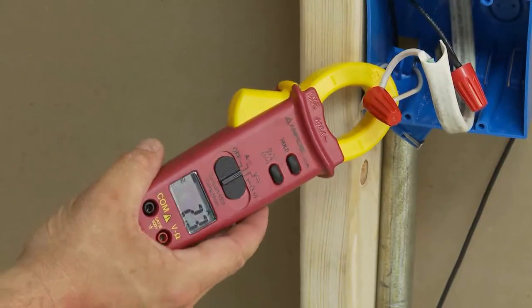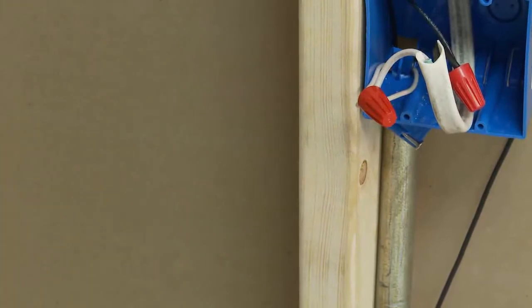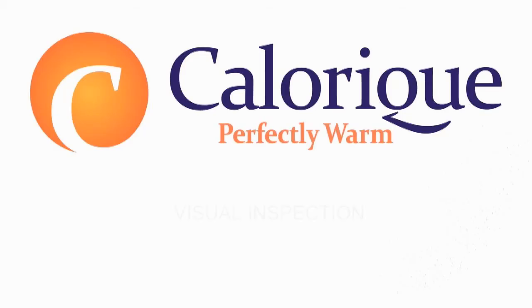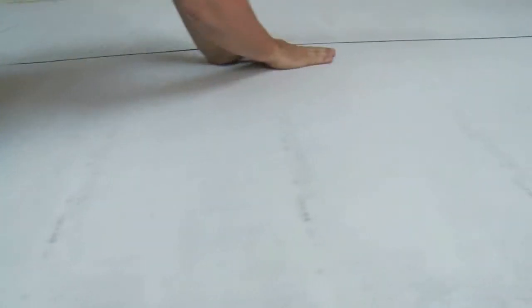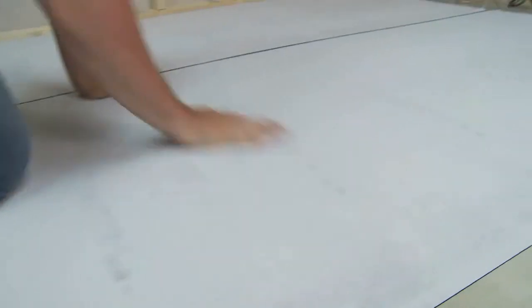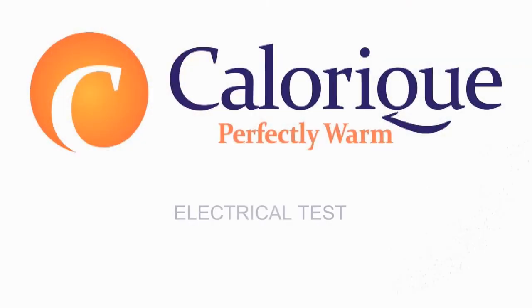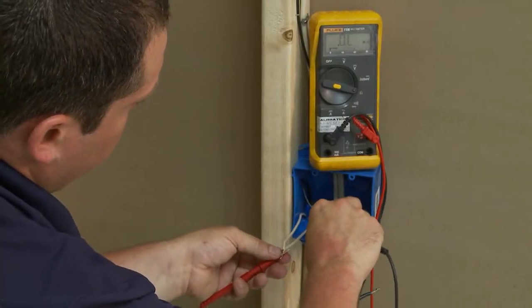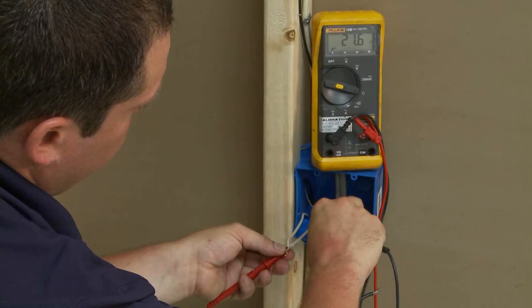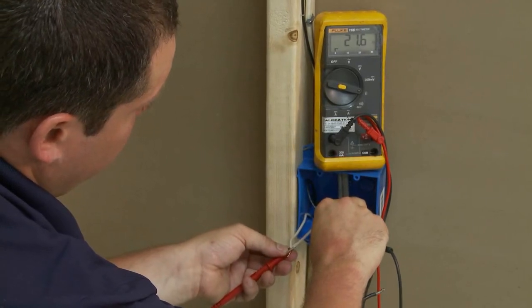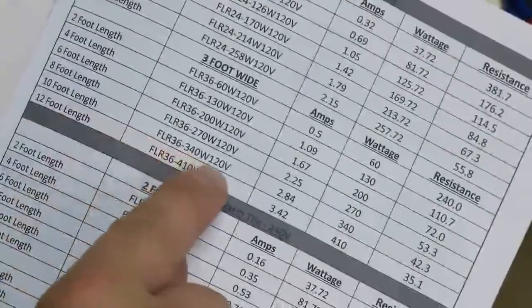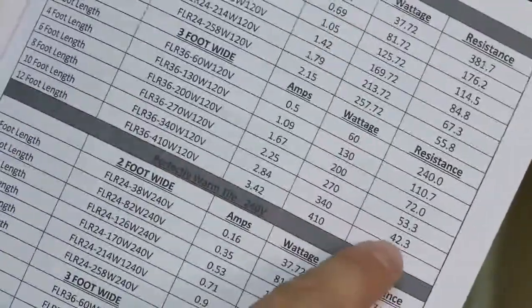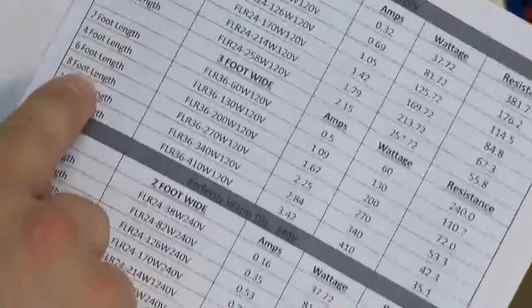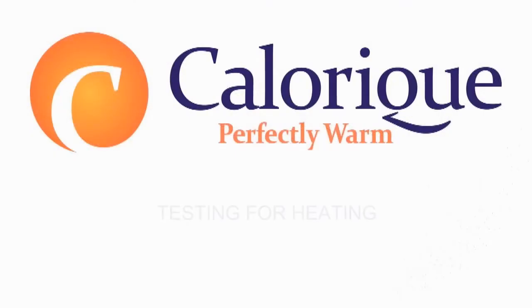A visual and electrical check must be performed on the heating mats prior to activation. Visual inspection. If any portions of a mat appear damaged, replace the entire mat. Electrical test. In order to detect any open circuits, use a digital ohm meter and conduct a resistance check across the supply leads of each mat. Record the resistance readings and use the resistance chart in the operating manual to determine the acceptable readings.